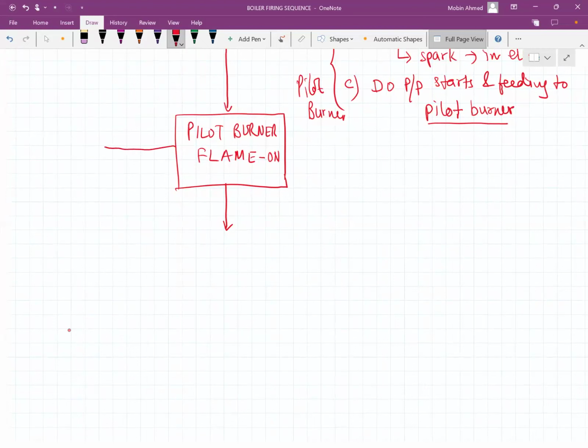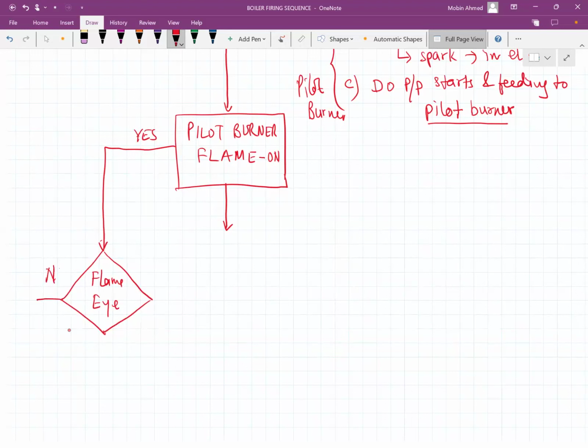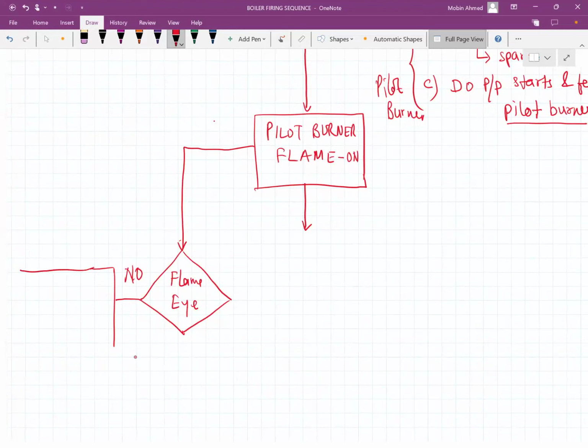There will be three lines I will be drawing together. One is the flame eye role, which comes here. Flame eye senses whether the flame is on - yes or no. If it is sensing yes, flame eye confirms the flame. If it is no, meaning the flame eye is not able to sense it, then ignition failure will occur, and this triggers the alarm.